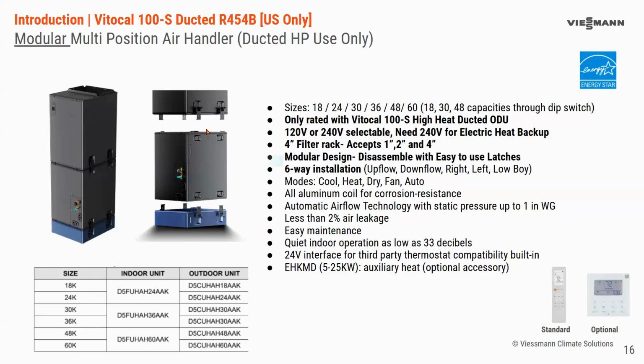And shown on the right is the unit's modularity, the ability for the unit to break down easily with these latches. So there's not a need to cut the unit or unscrew the unit or take all the components apart to get it up into an attic or down to a basement. That also plays into its installation flexibility. So you're able to actually do 6-way installation, and with some of those where you would previously have to move the coil or rearrange the coil, there's minimal requirement for that now, since you can actually put the blower motor above or below the coil. There's different ways to use those clips, if you will, the modularity of it.